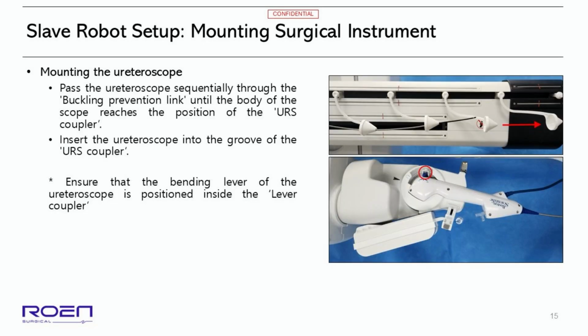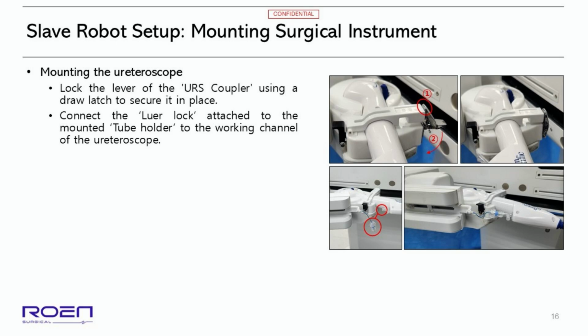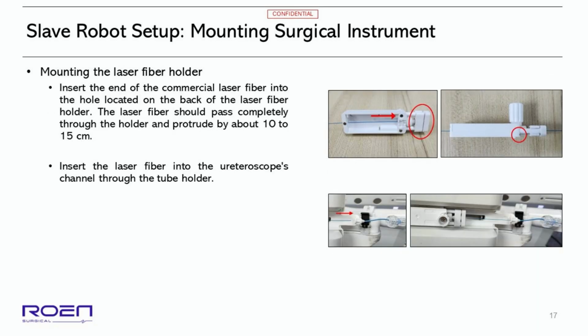Mounting the surgical instruments. First, the process for mounting the ureteroscope. Pass the ureteroscope through the buckling prevention links in order, then push it until the body of the endoscope reaches the URS coupler. Insert the ureteroscope into the URS coupler slot. The bending lever of the ureteroscope should be positioned to fit into the lever coupler. The lever of the URS coupler can be fixed using a draw latch. During the draping process, connect the luer lock, which is attached to the tube holder, to the working channel of the ureteroscope.